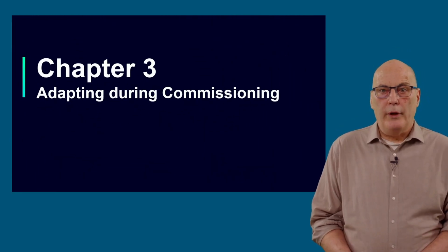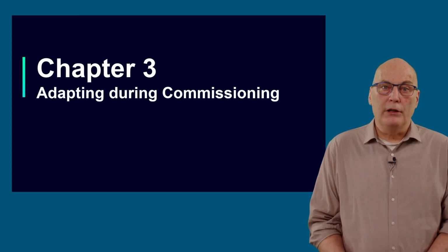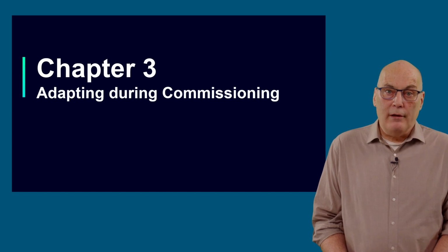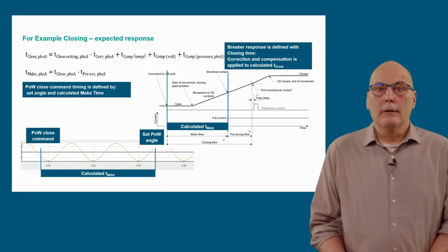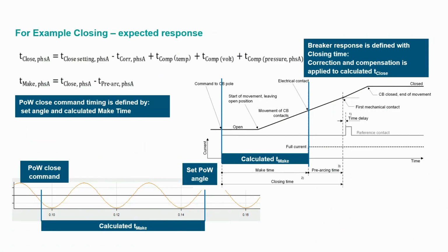To start off, we identify what the point-on-wave function is doing during its close cycle. First, it calculates the closing time based on the settings and the transducer inputs. This is the top equation. Sorry, I'm a little bit late. This closing time includes all influences and is the defining value for point-on-wave closing.